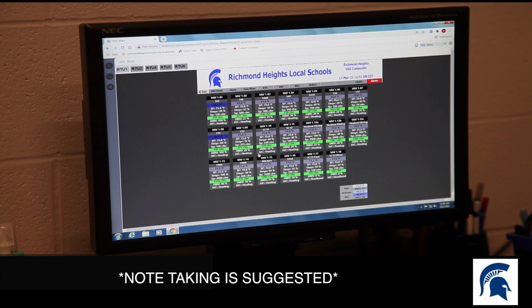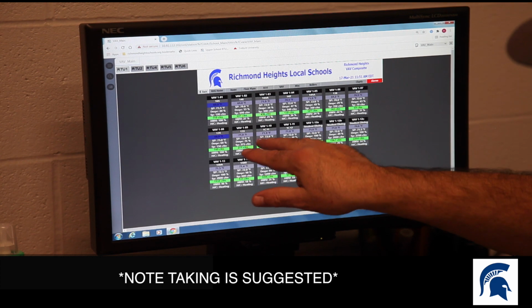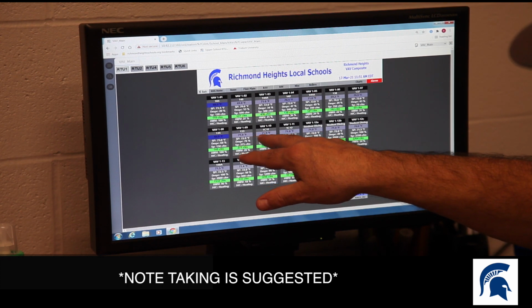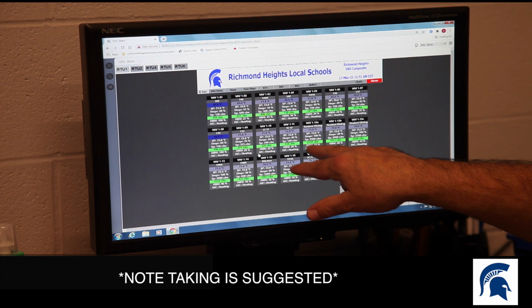So from this screen, you can't directly change anything. Right, it's just something to look at. Yeah, but if you go into one of the individual VAV graphics, you can click on any of the boxes on the page. I'm going to do that in 1 second. Yep. So what I'm seeing here is that these rooms probably have their thermostat set at 70 degrees or 71. Yeah, so, right, this one down below.